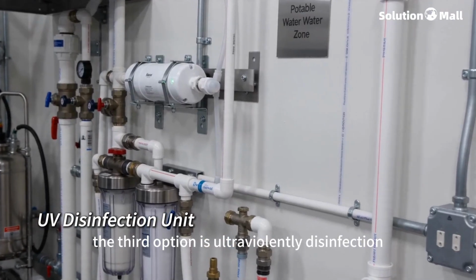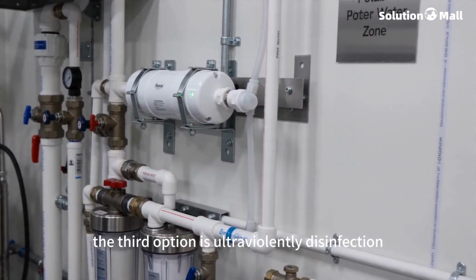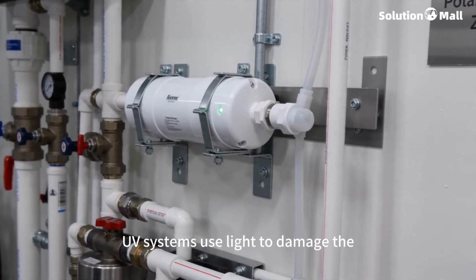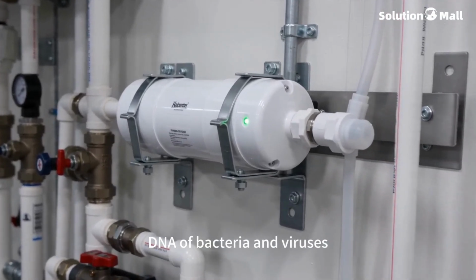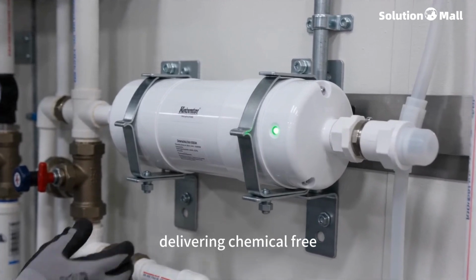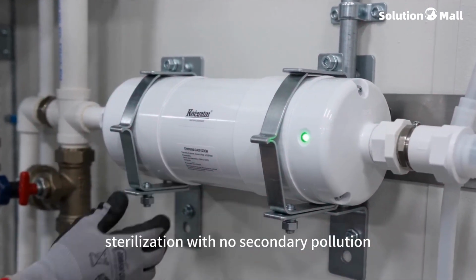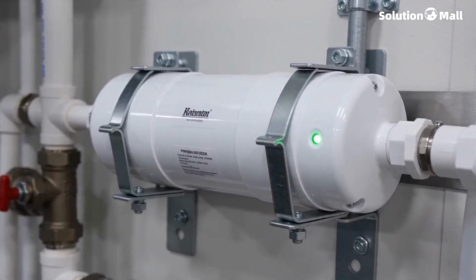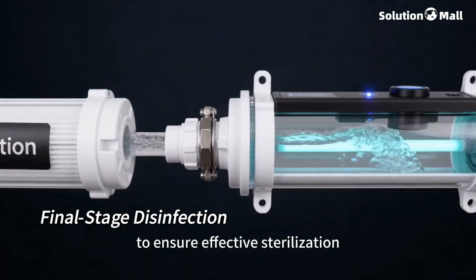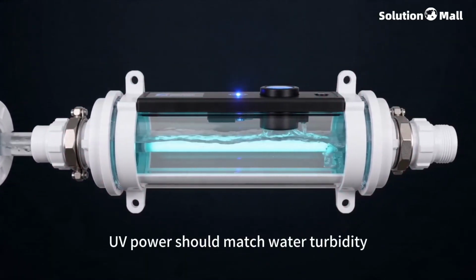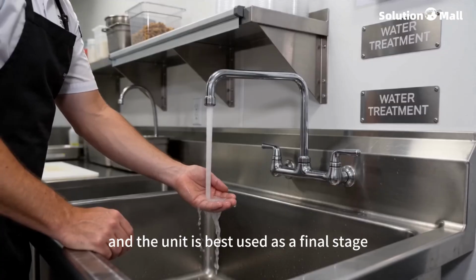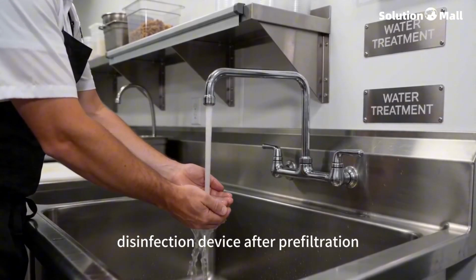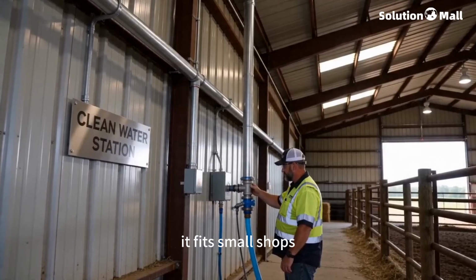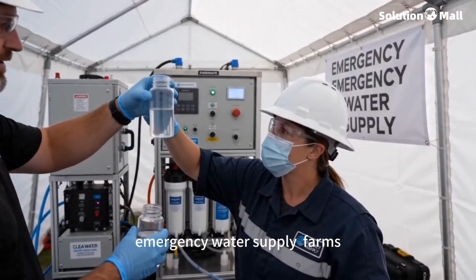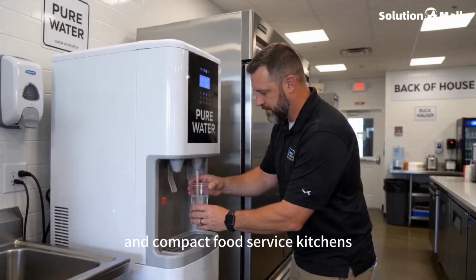The third option is ultraviolet disinfection. UV systems use light to damage the DNA of bacteria and viruses, delivering chemical-free sterilization with no secondary pollution. To ensure effective sterilization, UV power should match water turbidity, and the unit is best used as a final-stage disinfection device after pre-filtration. It fits small shops, emergency water supply, farms, and compact food service kitchens.